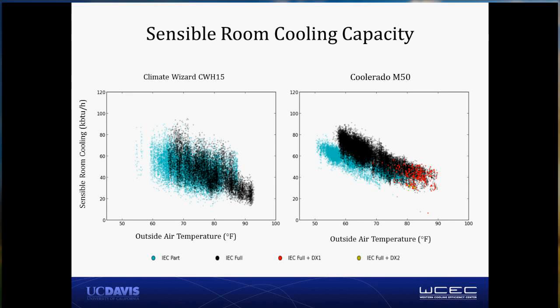So, of course, your room loads also increase as outside air temperature increases, and that adds up to the fact that you'll need some sort of supplementary cooling at peak in most applications to cover all of the room loads. In this case, of course, we have the DX on board that unit, plus all of the other DX units on the store operating in recirculation only to cover those room loads.